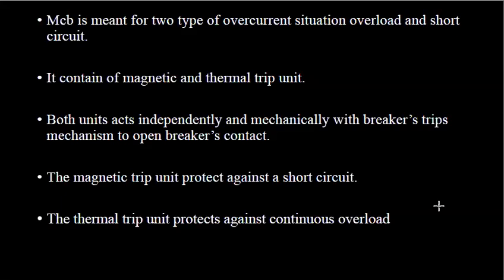And coming to the working of the MCB, whenever continuous overcurrent flows through the MCB, the bimetallic strip is heated and deflects by bending. This deflection of the bimetallic strip releases a mechanical latch. As this mechanical latch is attached to the operating mechanism, it causes the miniature circuit breaker contacts to open, and thus the MCB turns off, thereby stopping the current flow in the circuit. To restart the flow of current, the MCB must be manually turned on. So this mechanism protects from the faults arising due to overcurrent or overload.